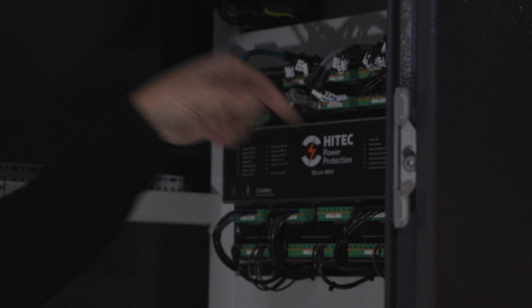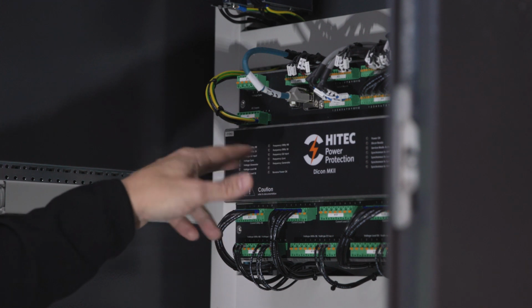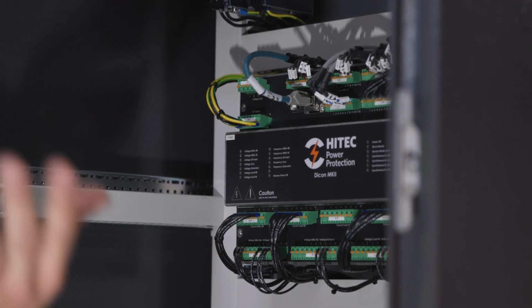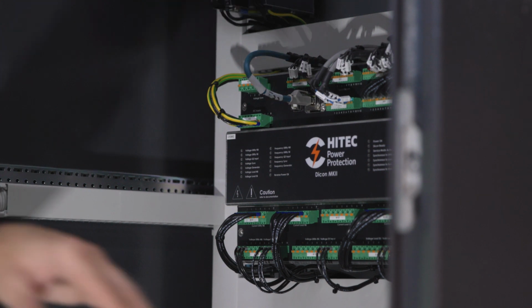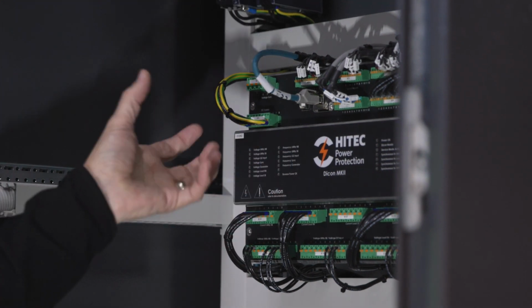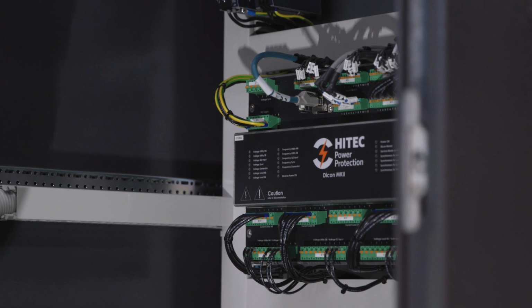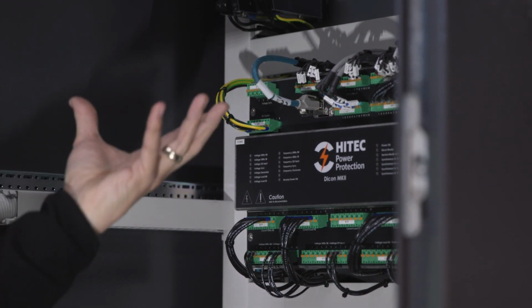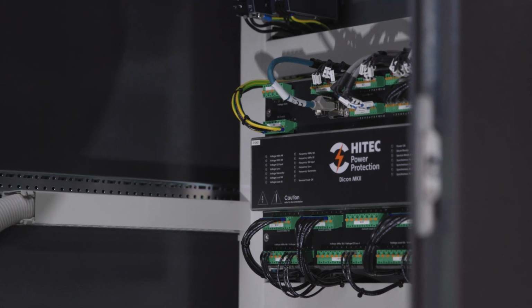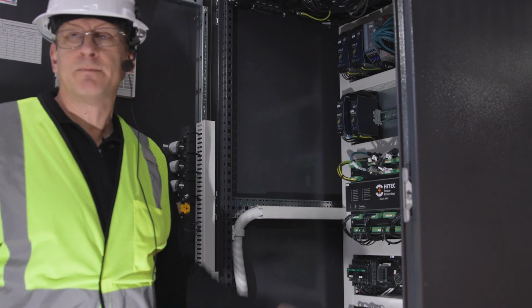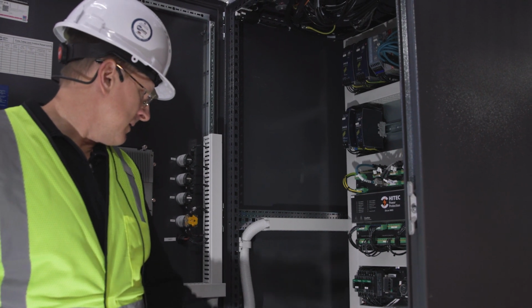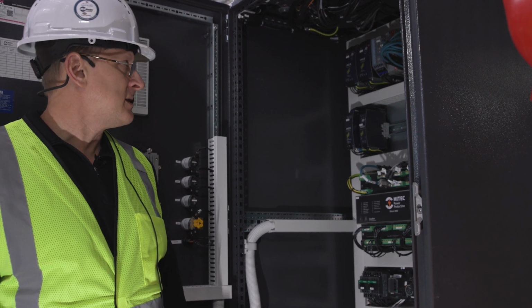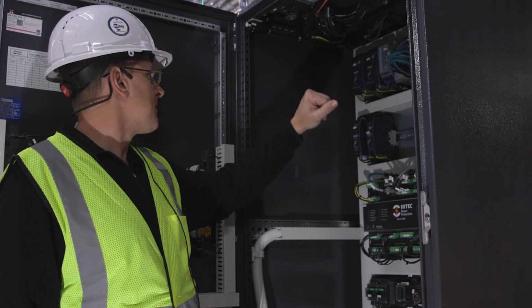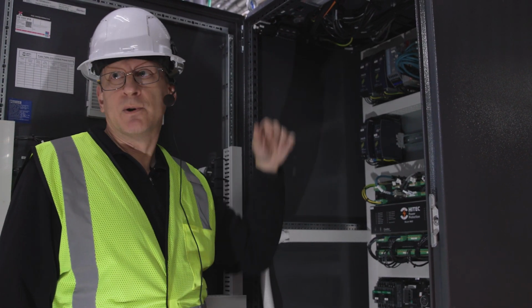You'll notice here it has a synchronous to utility light. So it can tell you when it's running synchronous with utility for closing Q1. It has other lights that don't apply to you. For dual output systems, it has short break as well, but that doesn't apply to you. But again, just some light indications that help our service guys troubleshoot certain parts of the system, or to give indications of the health of the system. They're kind of little cheat lights. And then there's just various other little devices: MCBs, protective devices, power supplies, network switches, and so forth.